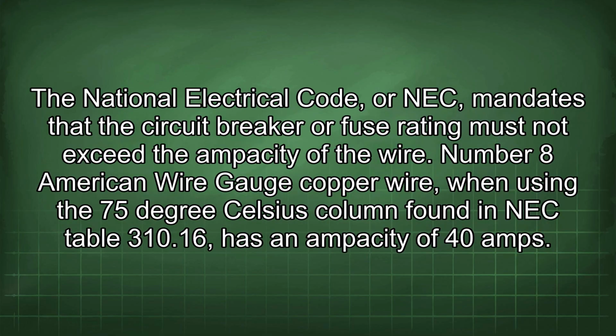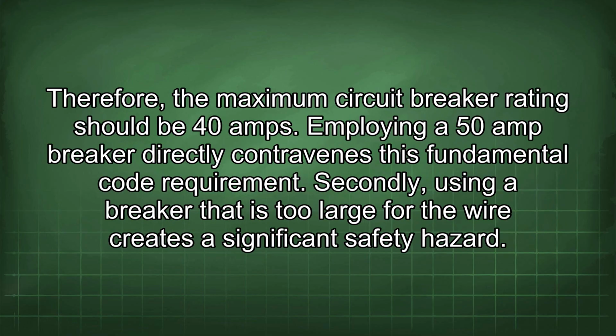The National Electrical Code, or NEC, mandates that the circuit breaker or fuse rating must not exceed the ampacity of the wire. Number 8 American wire gauge copper wire, when using the 75°C column found in NEC Table 310.16, has an ampacity of 40 amps. Therefore, the maximum circuit breaker rating should be 40 amps. Employing a 50 amp breaker directly contravenes this fundamental code requirement.